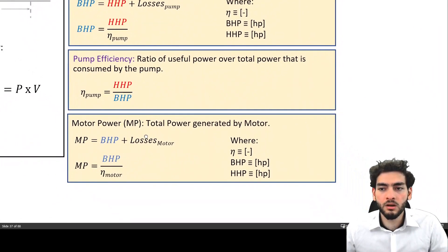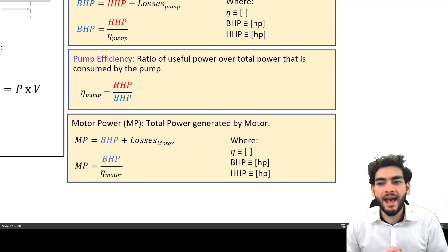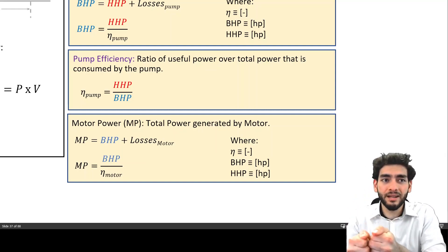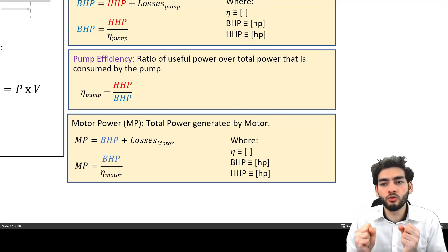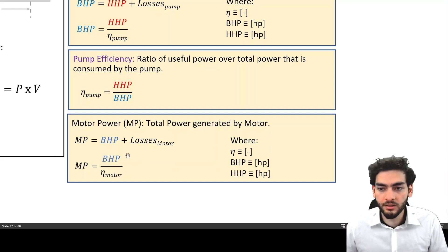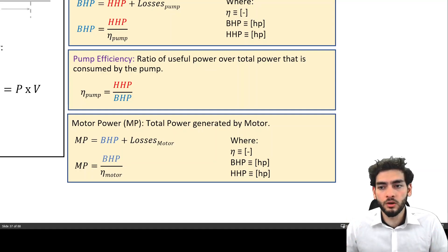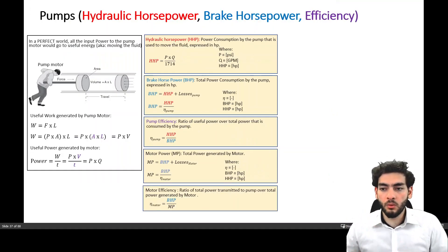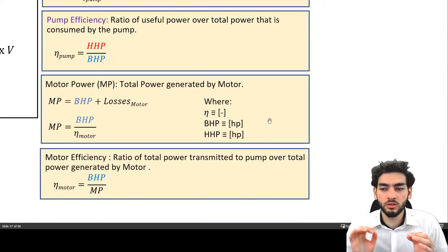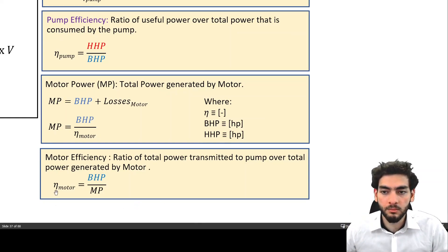The other power to be aware of is motor power, which is the total power generated by the motor. It includes the brake horsepower — all the power supplied to the pump — plus the inherent losses within the motor itself. There is another equation to express motor power if you know the motor efficiency. Motor efficiency is the ratio of the total power transmitted to the pump over the total power generated by the motor.